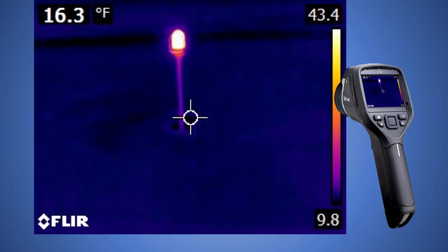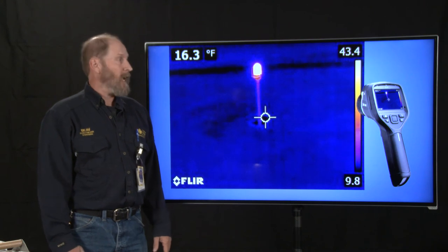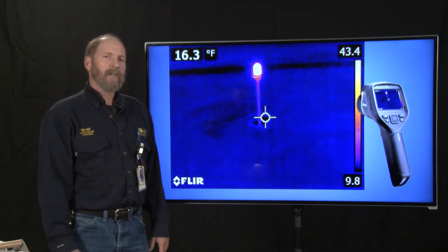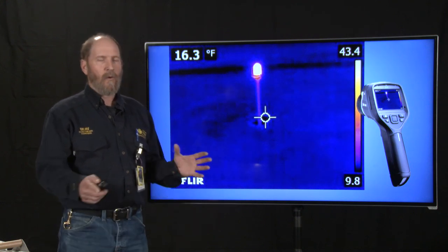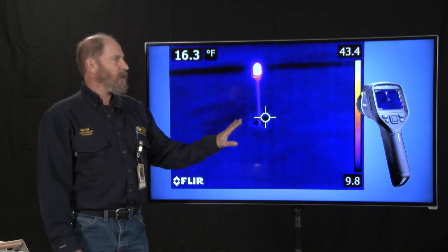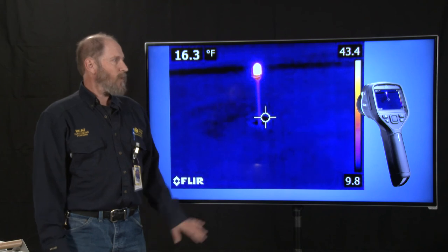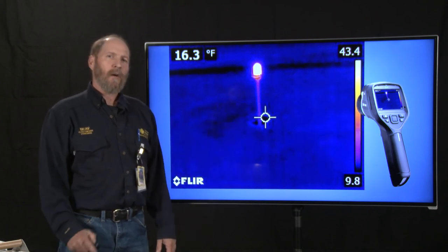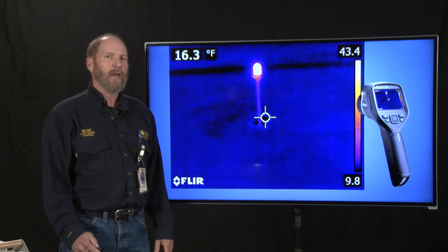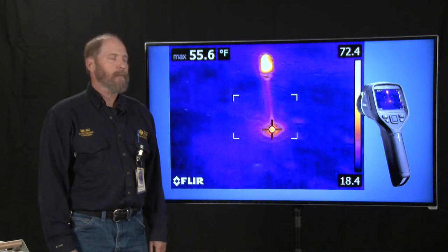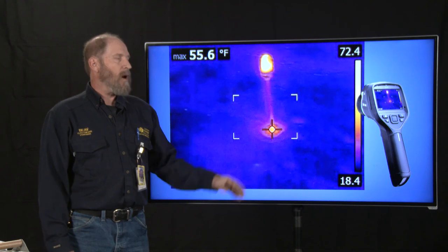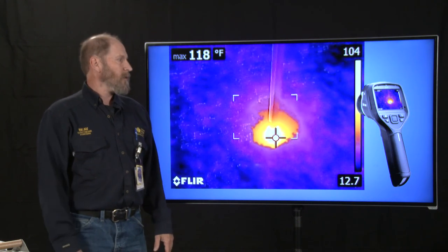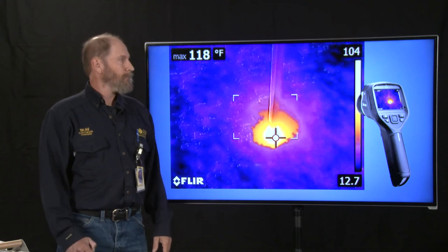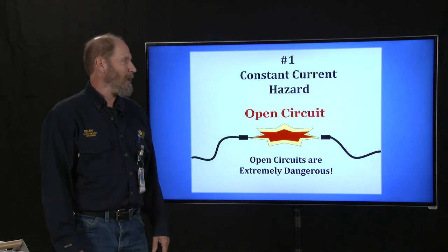I threw a few slides in here of just an interesting way that we've done some troubleshooting. We have a FLIR camera. It's a forward-looking infrared camera. In the wintertime, it's very difficult to troubleshoot our lights because we have ice in the cans, snow all around. It's hard to find problems. So we started driving around with this camera hanging out the window, pointing at the different lights, and we found that if there was a problem in the can, especially an isolation transformer fault, it would start to show up as heat at the base of the can. So this particular one was a pretty mild isolation transformer fault. This particular one was 118 degrees. It was actually on fire under the ground, and we were able to find it pretty quickly. So it's a good tool, just handy. I just threw that in because I thought you might like it.